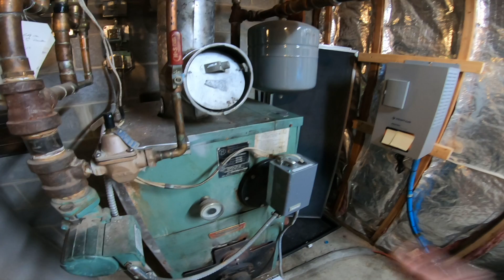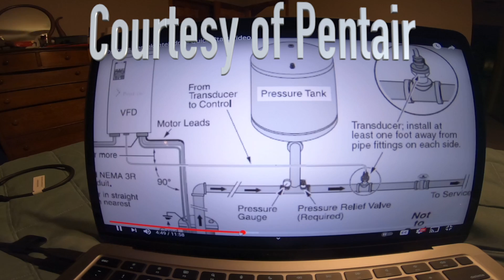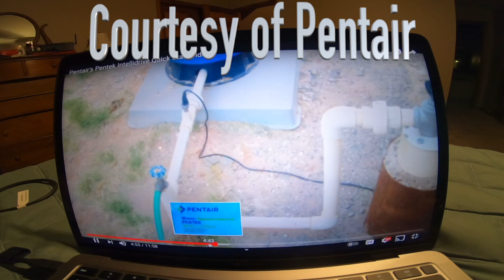Right now it's summertime, so it's not such a big deal. But it's going to be winter, and it's going to be very cold over here. Make sure that when installing the transducer that it is installed after the tank and directly in the flow of water on a straight run pipe. You don't want to float the transducer, install before the tank or before a tee, as these situations will not provide the Pentek Intellidrive with accurate readings, and therefore the unit will not function correctly.